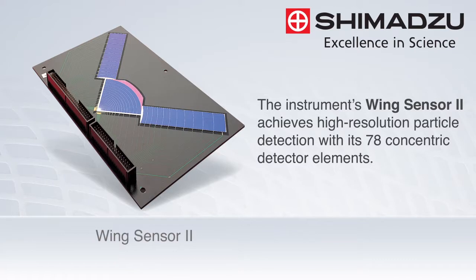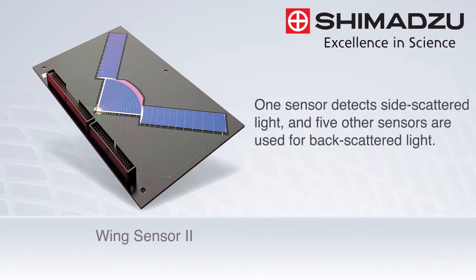The instrument's Wing 2 sensor achieves this with its 78 concentric detector elements. One sensor detects side-scattered light, and five other sensors are used for backscattered light.